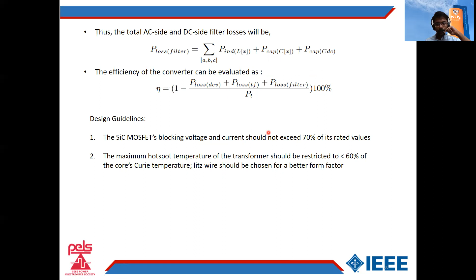Now, in the design guidelines, two important things to note are that the SiC MOSFET's blocking voltage and current should not exceed 70%, and the maximum hotspot temperature should be restricted to less than 60% of the Curie temperature, and litz wire should be chosen for a better form factor.